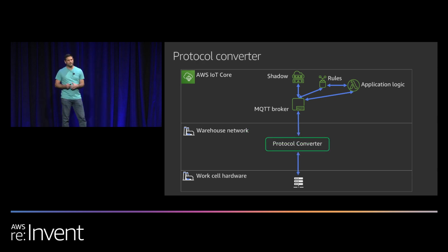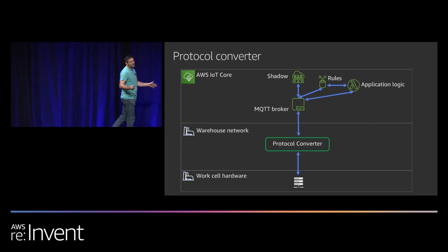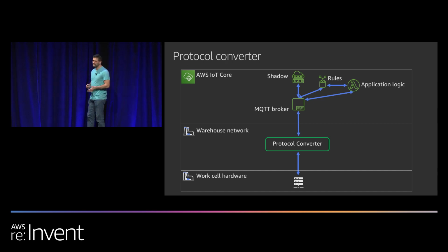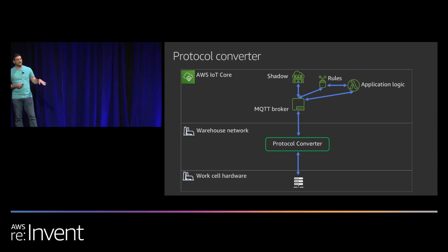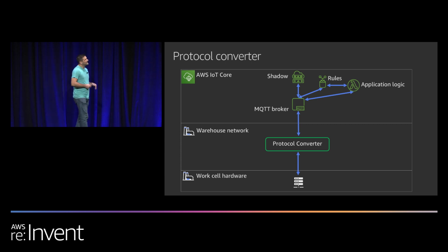That's where the protocol conversion process comes in. So we're going to take that Ethernet IP Modbus message and convert it into MQTT TLS, and we're going to take advantage of the fact that we probably have a service running somewhere in the building that already has access to the firewall in order to do your WMS software management of that device, and which could have cloud access, and that thing will work as a proxy.